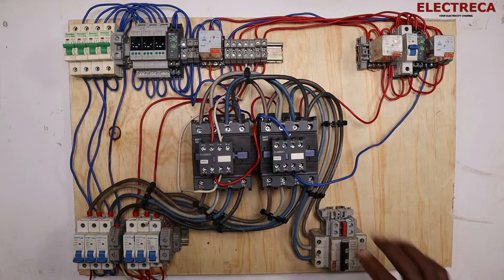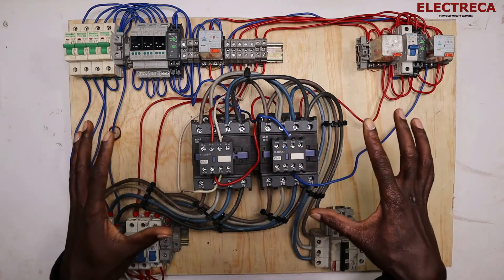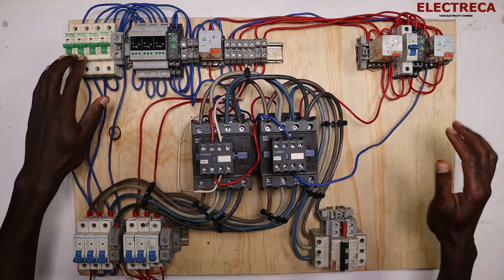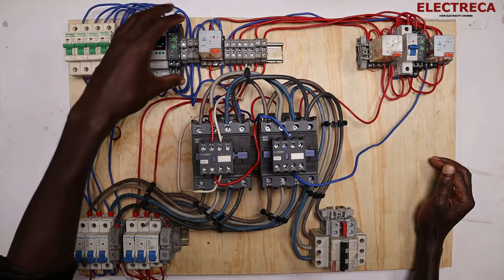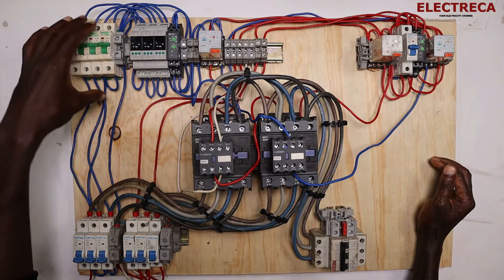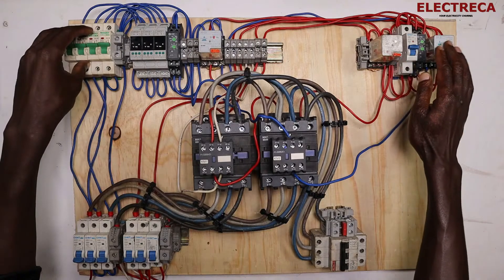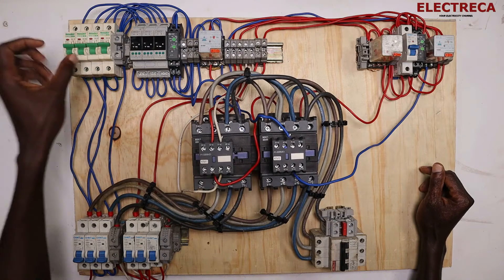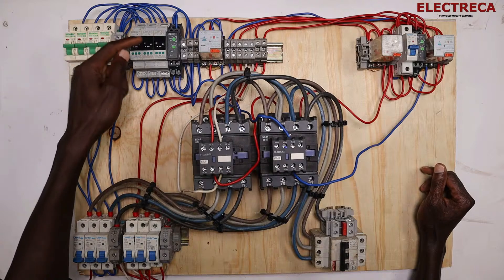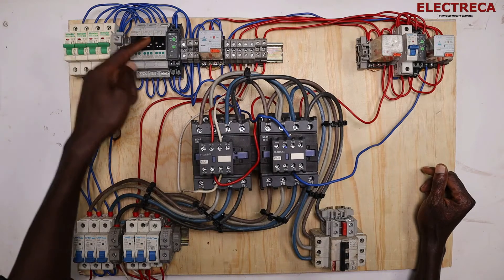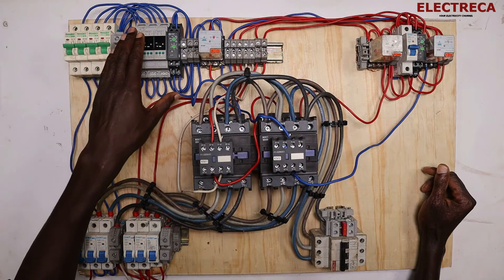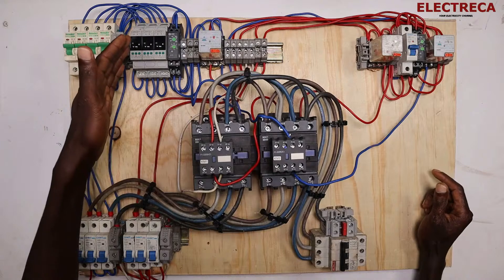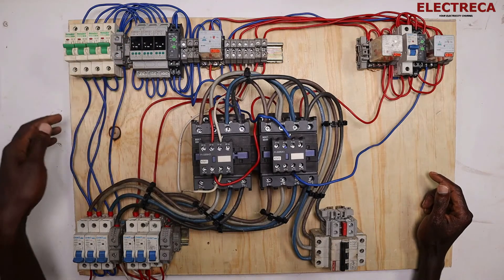Now let us look at the control circuit. We have two control circuits — the blue wires are the mains control circuit and the red wires are the generator control circuit. In the generator control circuit, we have three breakers supplying individual voltage comparators and then a fourth control breaker. The comparators are constantly monitoring voltage in this circuit to make sure that voltages are in the normal ranges.